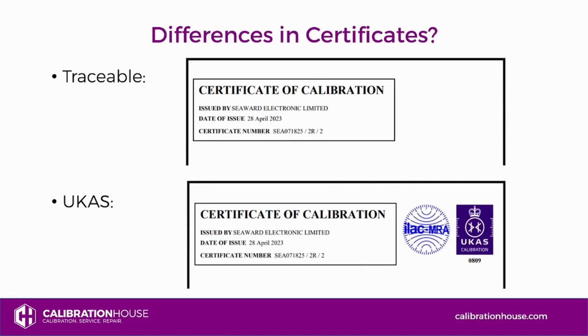A UKAS and a traceable certificate will have certain differences. With a traceable certificate, you won't see the UKAS logo. This is the most obvious distinction between a traceable and a UKAS certificate. If you see the UKAS logo or symbol, which you can see in the second image here, the second example, that tells you that the certificate is a UKAS calibration. If that logo isn't present, it's not a UKAS calibration.